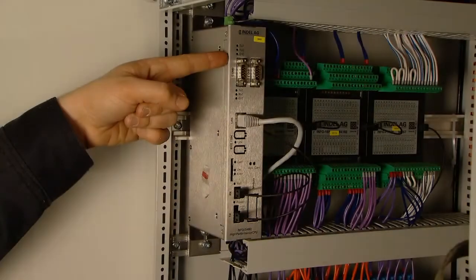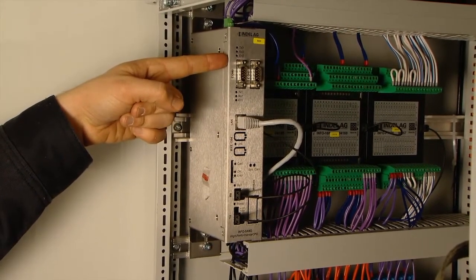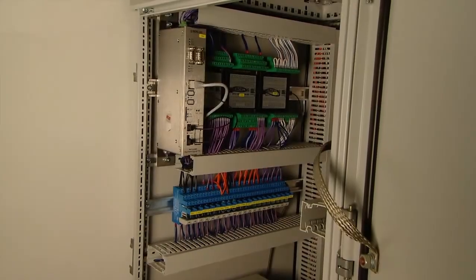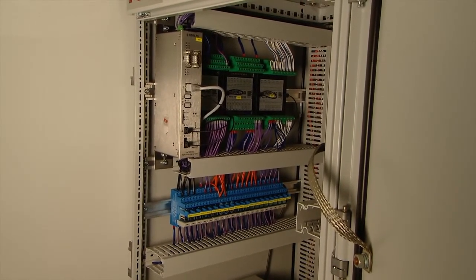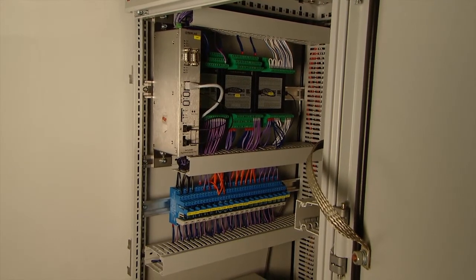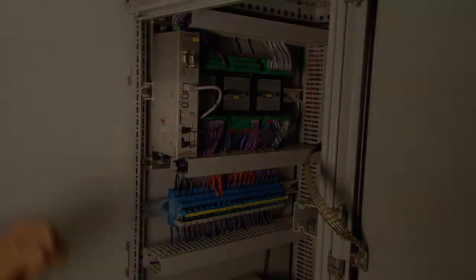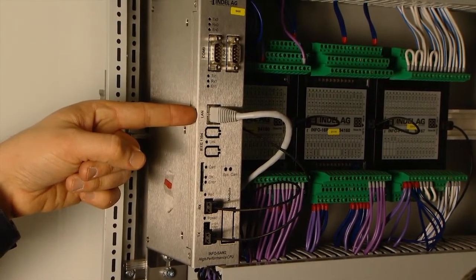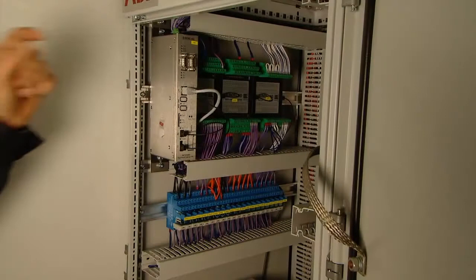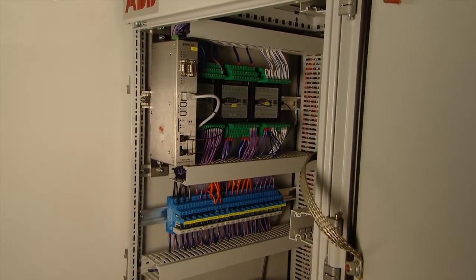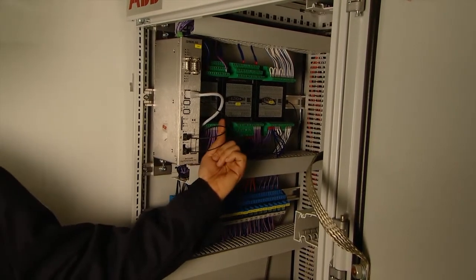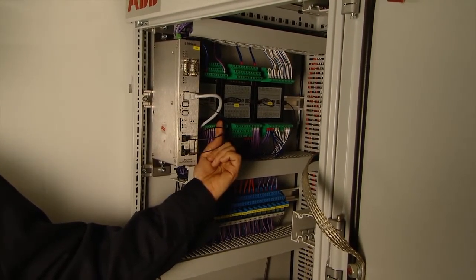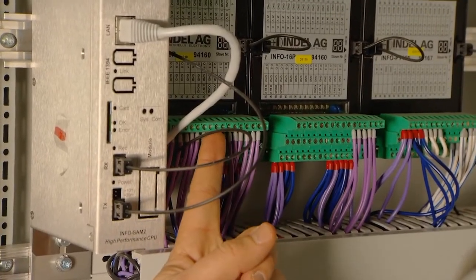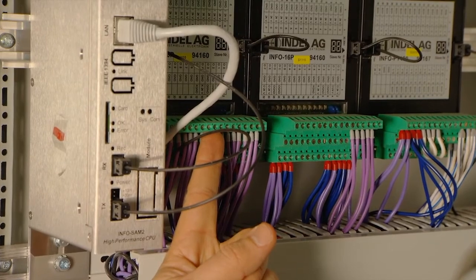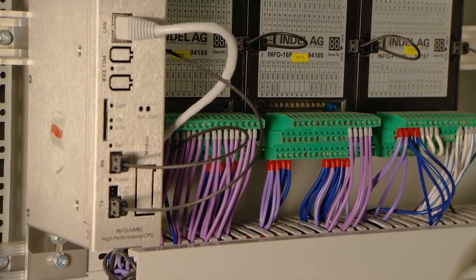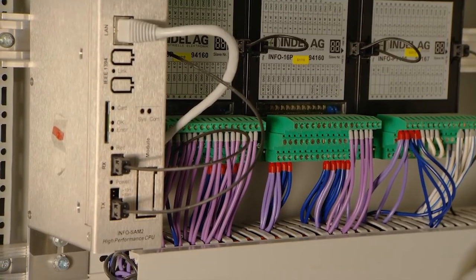This part here is a master control for the entire LFH plant. It controls the converter, and it also controls all the external devices. It communicates with all the input-output boards through an optical link, and it communicates with the laptop over an Ethernet cable. The input-output cards are connected over the optical link and are placed throughout the converter and throughout the control cabinet. This is a digital input-output card. It has 16 inputs and 16 digital outputs. There are separate cards for the analog inputs and outputs, and also for the temperature sensor inputs and outputs.